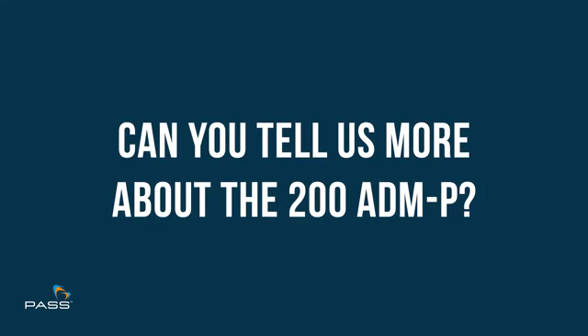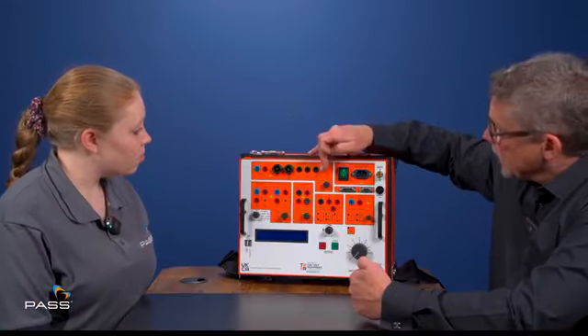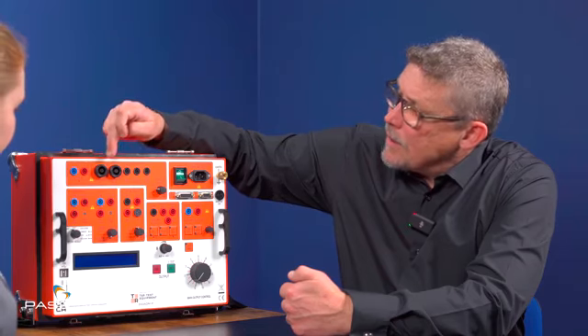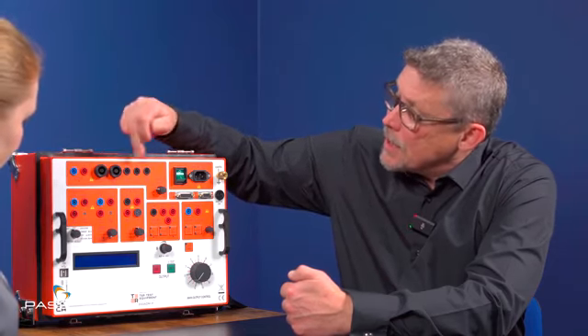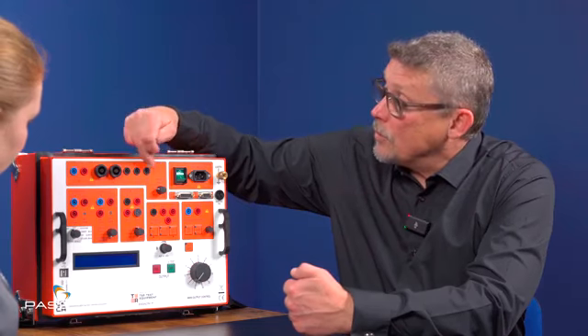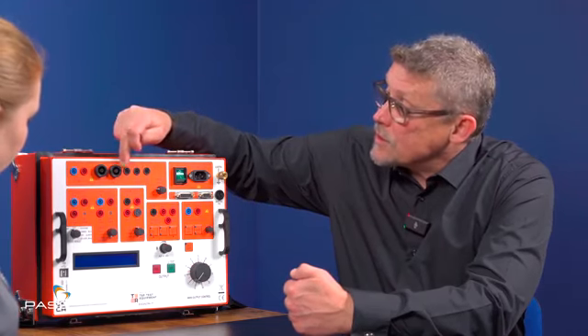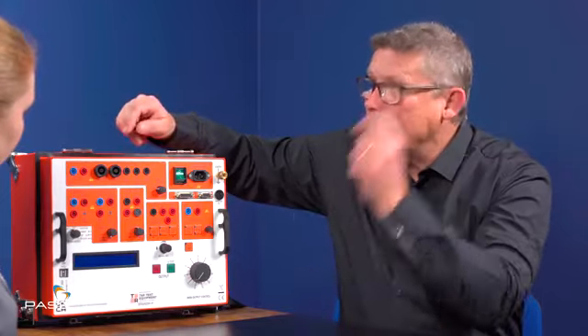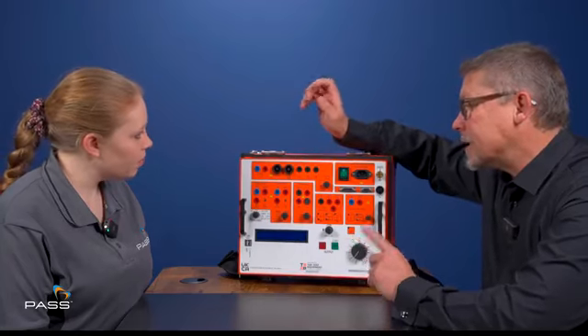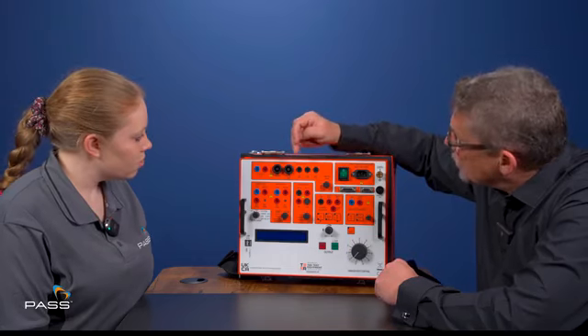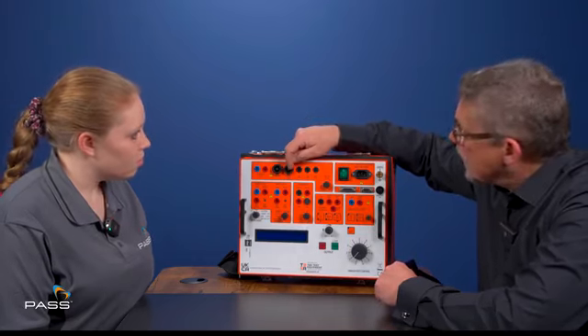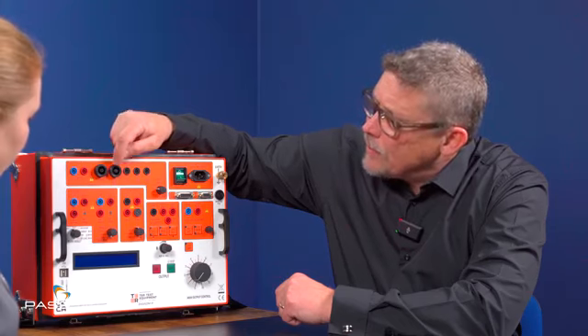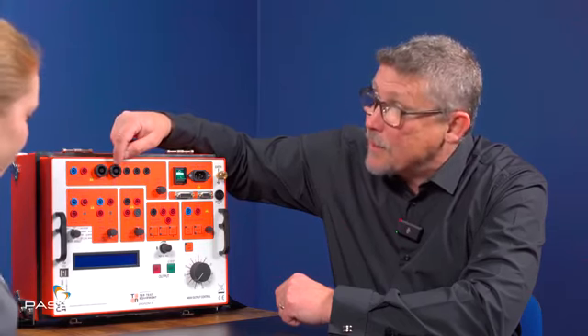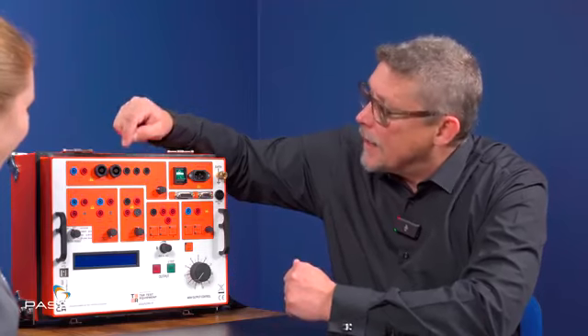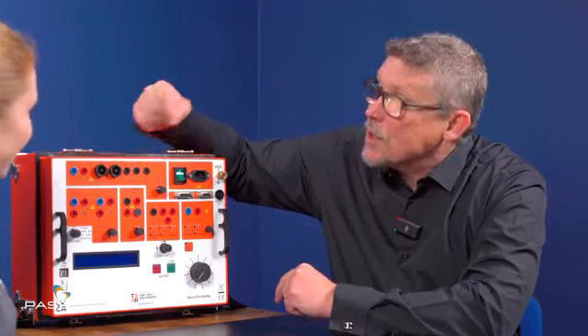Okay, so could you tell us about the 200ADM-P, please? Yeah, so as I said, we've got this main output here. So the main output here has a common and then a number of taps. This is the first misnomer that people fall foul of. When they're trying to test a relay, they look at it and they're thinking, I want current. They forget that actually to get the current, they need the voltage. So, for example, they'll look and go, this is a 200 tap, and they actually want 35 amps. And when they find they're not getting 35 amps from that tap, they panic and they won't do it. And they forget actually it's the voltage that will give you the current.